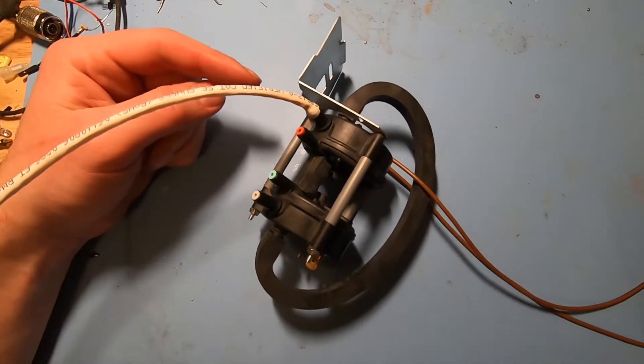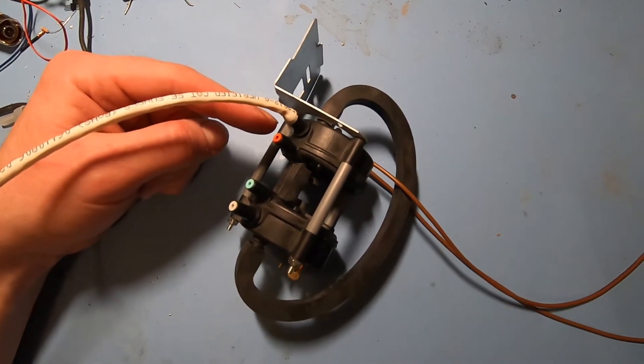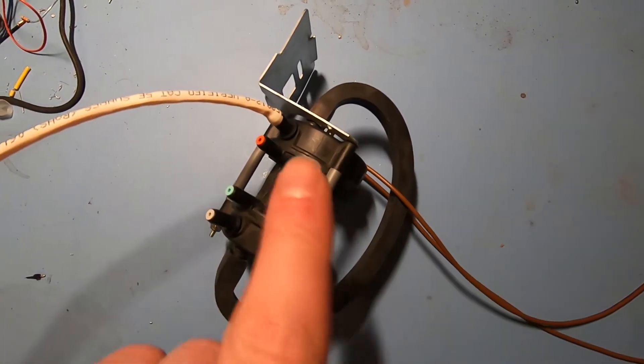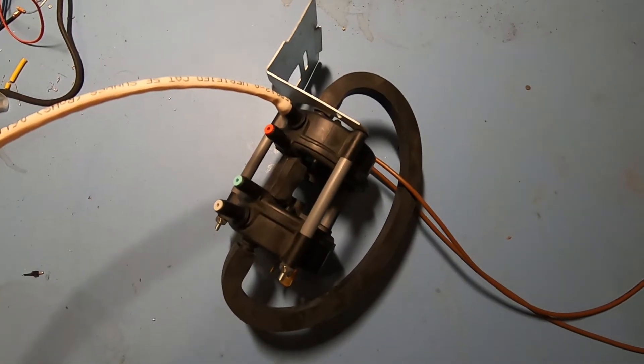Here's the pressure switch on my bench. This back switch right here is the high pressure switch. I got my multimeter hooked up here, and I got a little tube here that I'm going to blow into so we can test it.